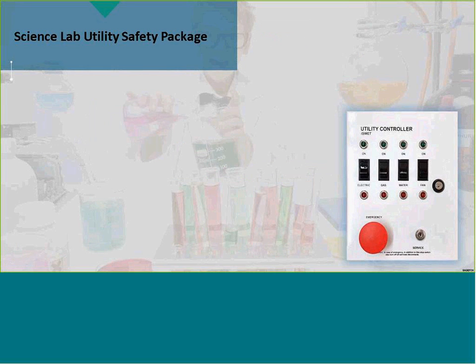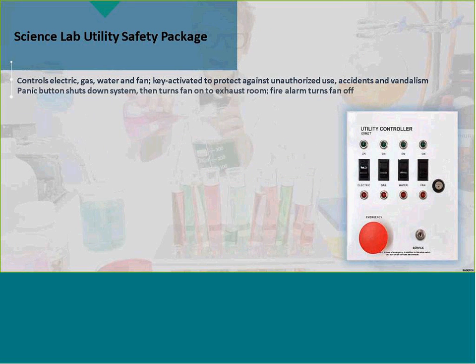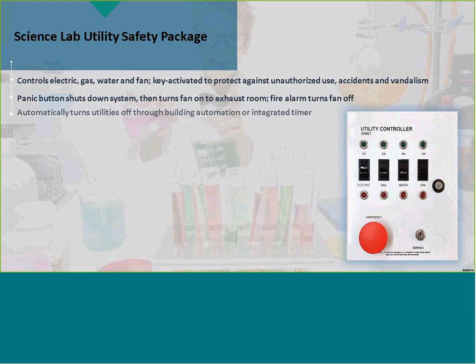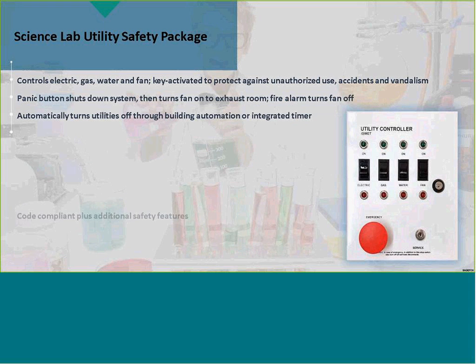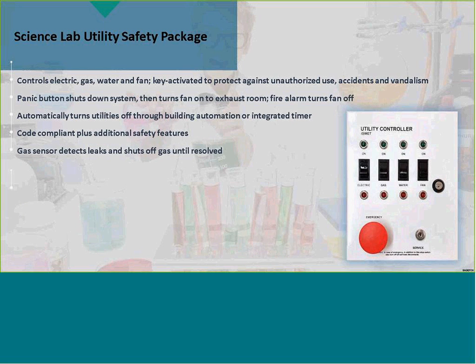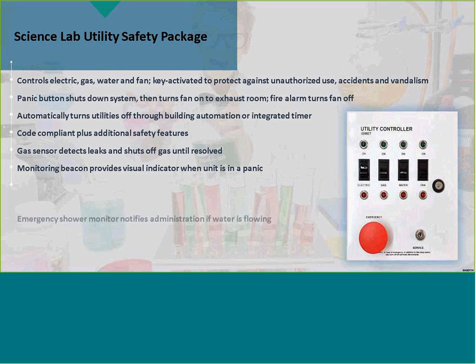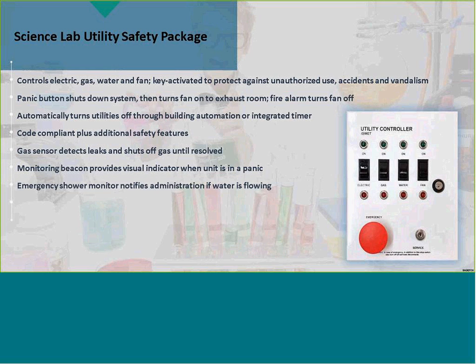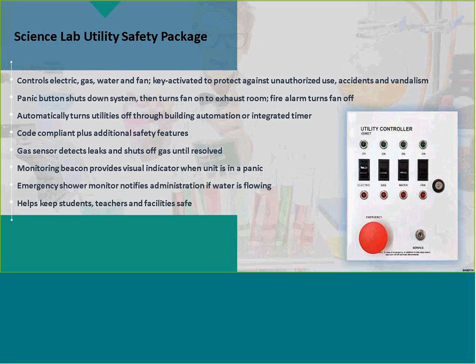So just to recap what we discussed: we're controlling electric, gas, water, and fan. You have to have a key to activate the system, and it can only be done by an authorized person so accidental vandalism doesn't occur. Make sure you have enough panic buttons around so the system can be turned off, and they also activate exhaust fans for experiments that may require extra exhaust to get rid of fumes. Of course, during a fire alarm situation, you don't want that fan on.